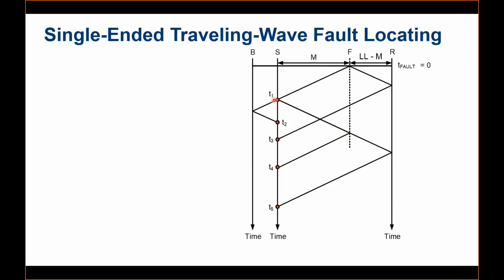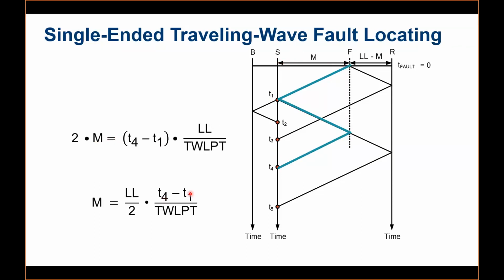If the relay measures the times T1 and T4, then with that empirical relationship you can solve the equation for the value M, which is the faulted point from the station S. So if you know T4 and T1 with those reflections, the relay can easily give you the information on the fault point. This is much more accurate, and it is not dependent on remote relay communication. This is one of the methods that we use to detect the fault location precisely if you don't have a connection between two relays, or if you have a single relay.